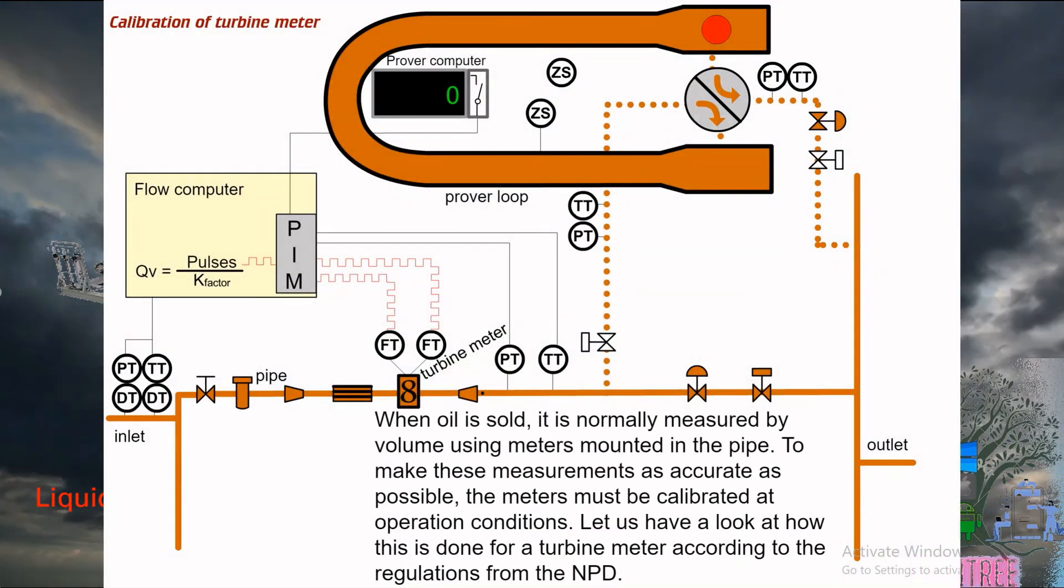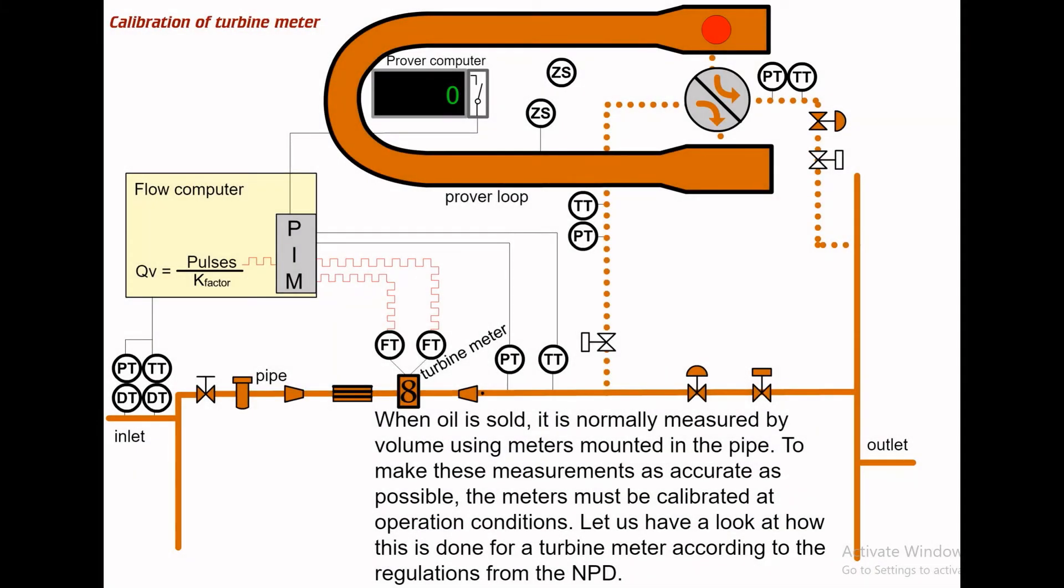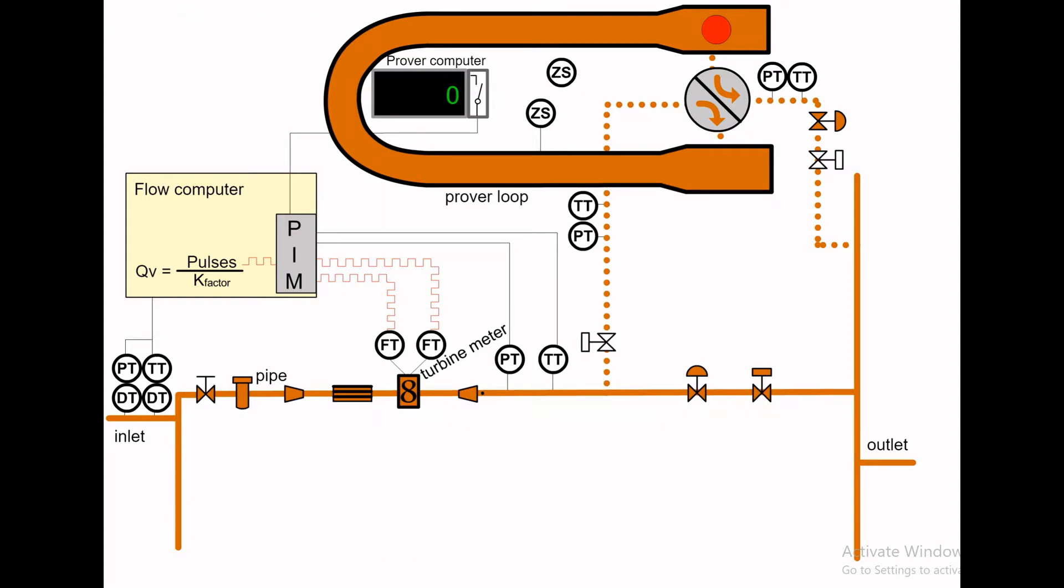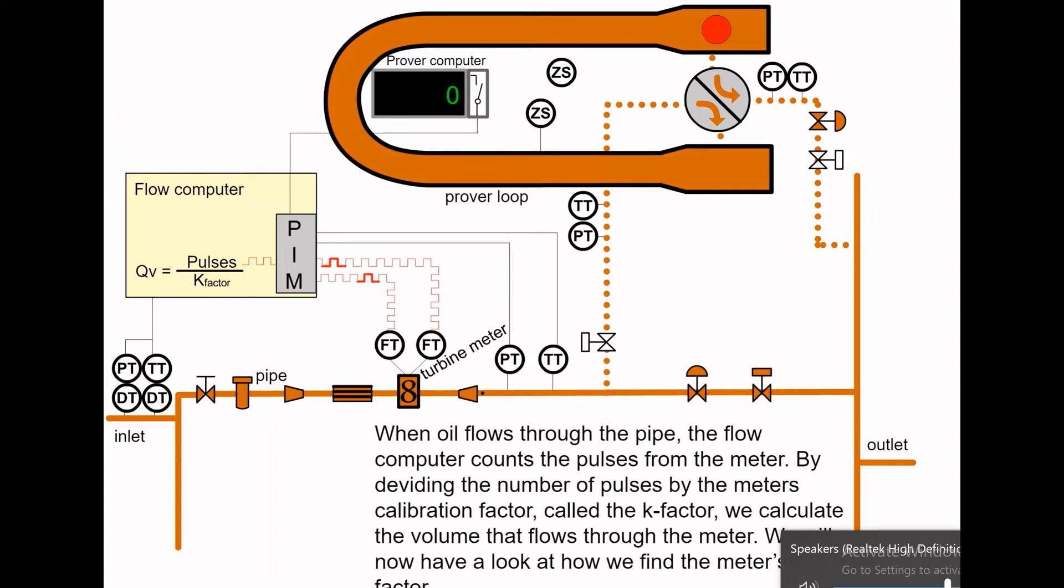Let's have a look at how this is done for a turbine meter according to the regulations from the Norwegian Petroleum Directorate. When oil flows through the pipe, the flow computer counts the pulses from the meter. By dividing the number of pulses by the meter's calibration factor, called the k-factor, we calculate the volume that flows through the meter. We will now have a look at how we find the meter's k-factor.